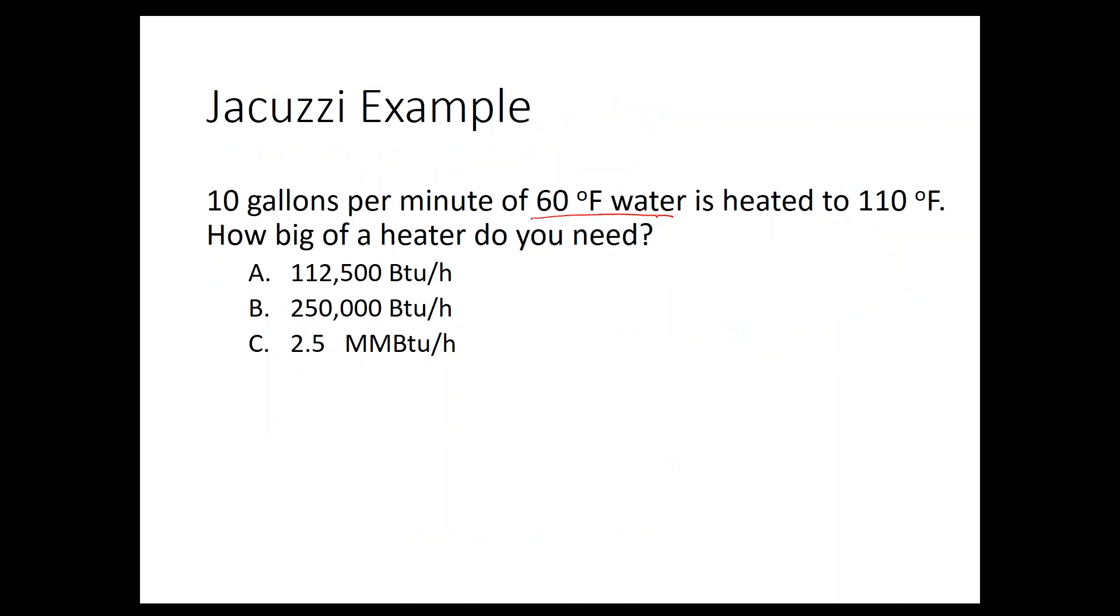I like to apply this equation into what I call a jacuzzi example. Say you've got 60 degree water coming from the ground, and you want to heat that to 110 degrees. Say you want a flow rate of 10 gallons per minute. So the question is, how big of a heater do you need? If you've done this before, pause the recording. If not, let's do the equation. Q equals 500 GPM times delta T. If you multiply all these things together, you get 250,000 BTUs per hour.